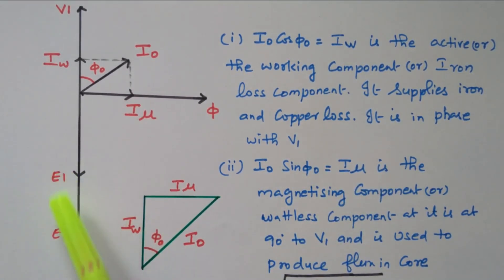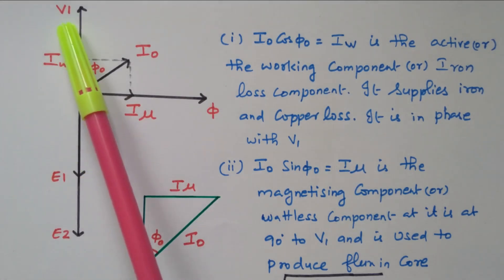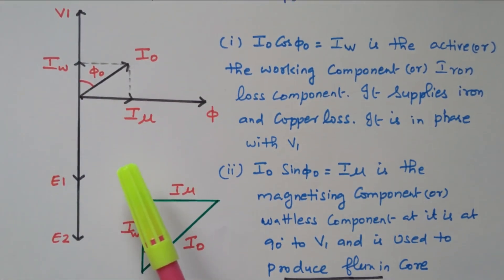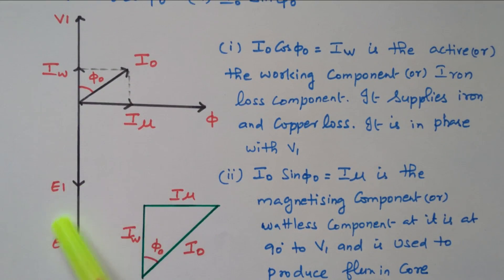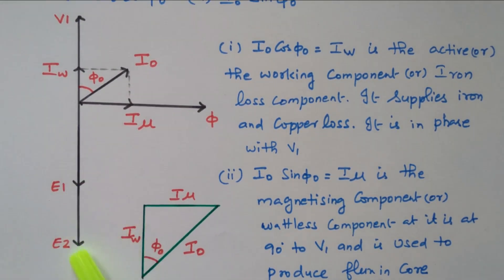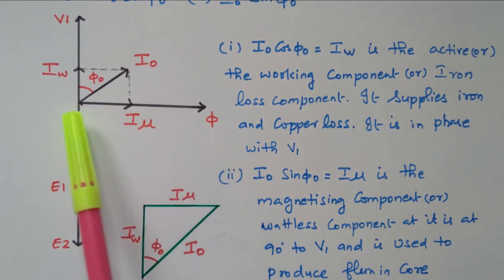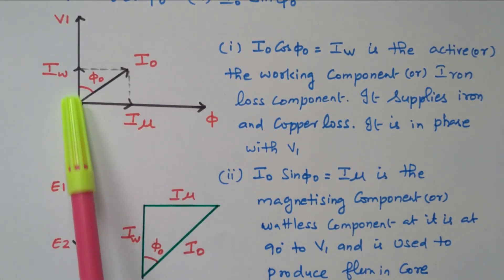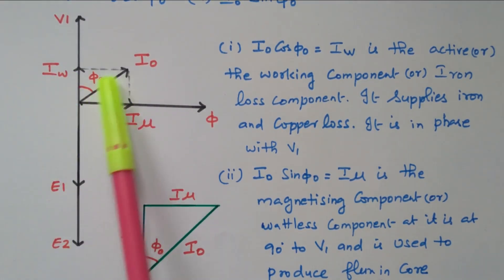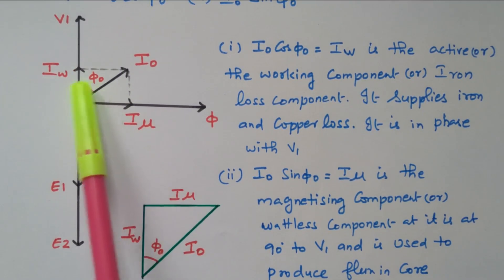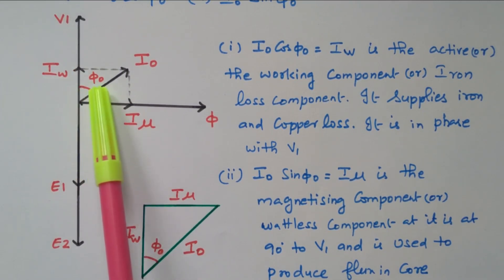The induced EMFs E1 and E2 are opposite to V1 because, based on Faraday's law and Lenz's law, the induced EMF opposes the flux producing it — so it is available in the opposite direction. The magnetizing current is in phase with the flux, the working current is in phase with the voltage, and the vector sum of these two is I0, with a phase angle of phi0 between I0 and V1.